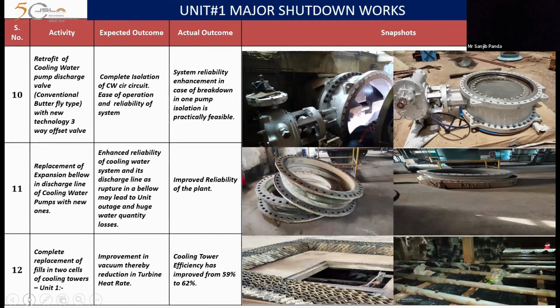Then retrofit of cooling water pump discharge valves. The conventional butterfly type valves have been replaced with three-way offset valves, which has increased the system reliability in case of breakdown in one of the pumps. Now we are able to positively isolate and work on the affected pump. Then next is replacement of expansion bellows in the discharge line of cooling water pumps with new ones. This has also improved the reliability of the plant.